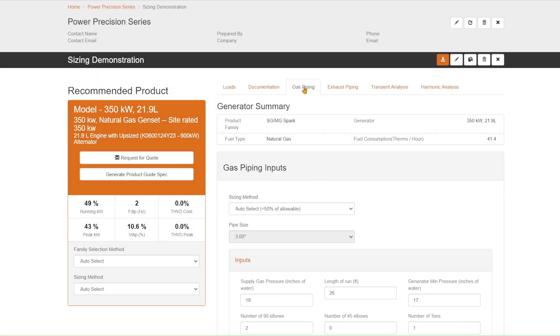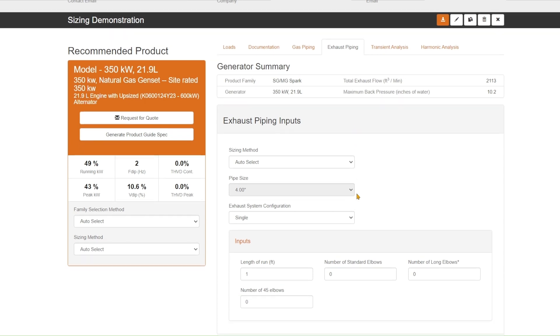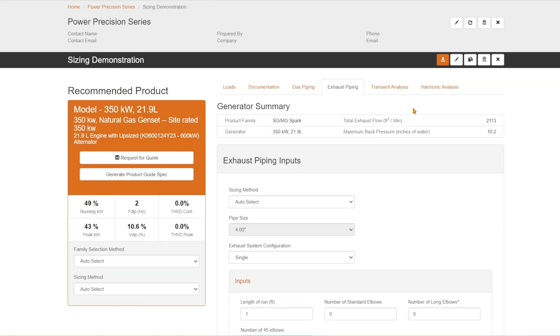If this is a gas solution, this is a tab that allows you to help figure out what is the gas piping design that you're going to need that's adequate to supply fuel for the unit. If the unit is going to need exhaust pipe extension, being it in the building and running out of the building or out of a building and running up the side, this is what we would use to be able to make those determinations to ultimately tell you what size pipe you're looking for.